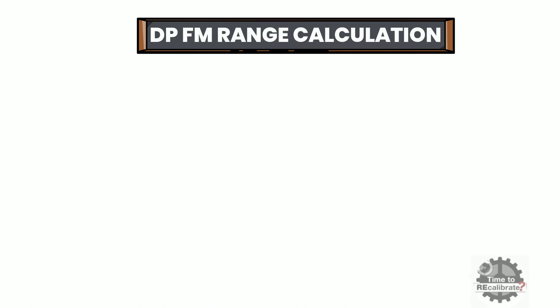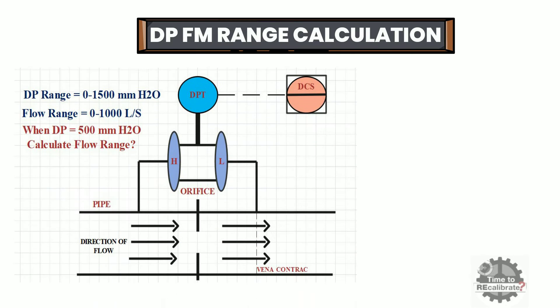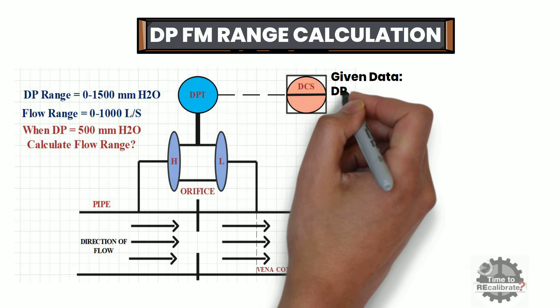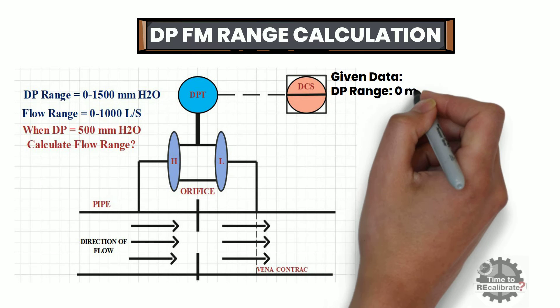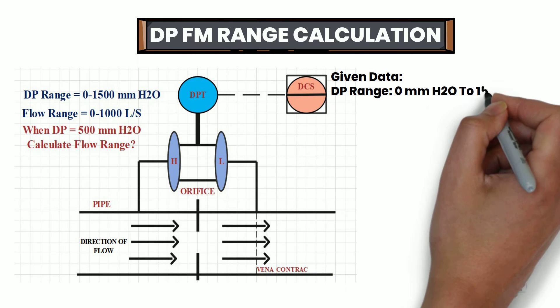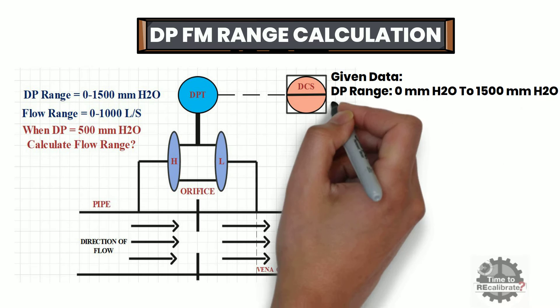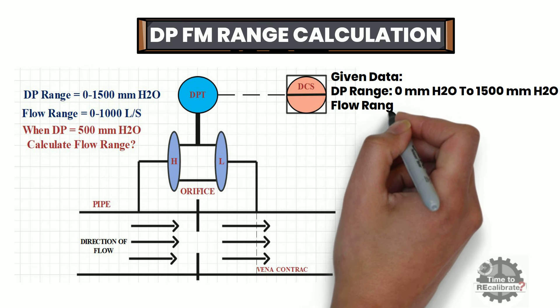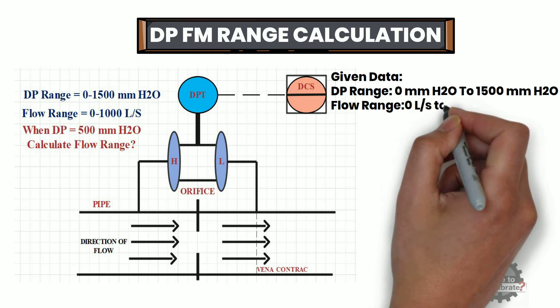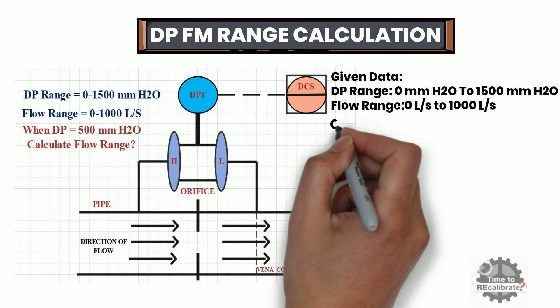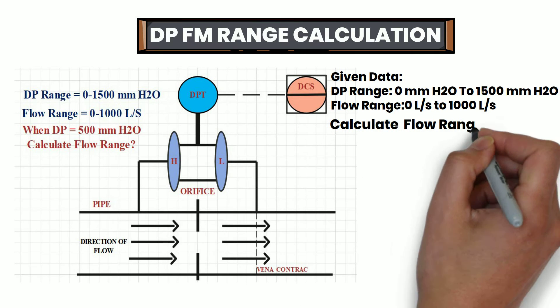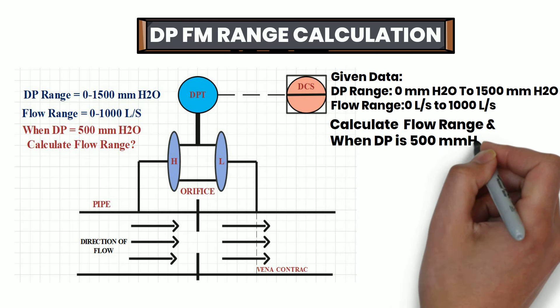Let's take one example to understand the range calculation method of a DP flow transmitter. As you can see from this diagram, the differential pressure range is 0 to 1500 mm H2O for this DP transmitter, and the flow range is 0 to 1000 liters per second. We need to calculate the flow range when differential pressure is 500 mm H2O.